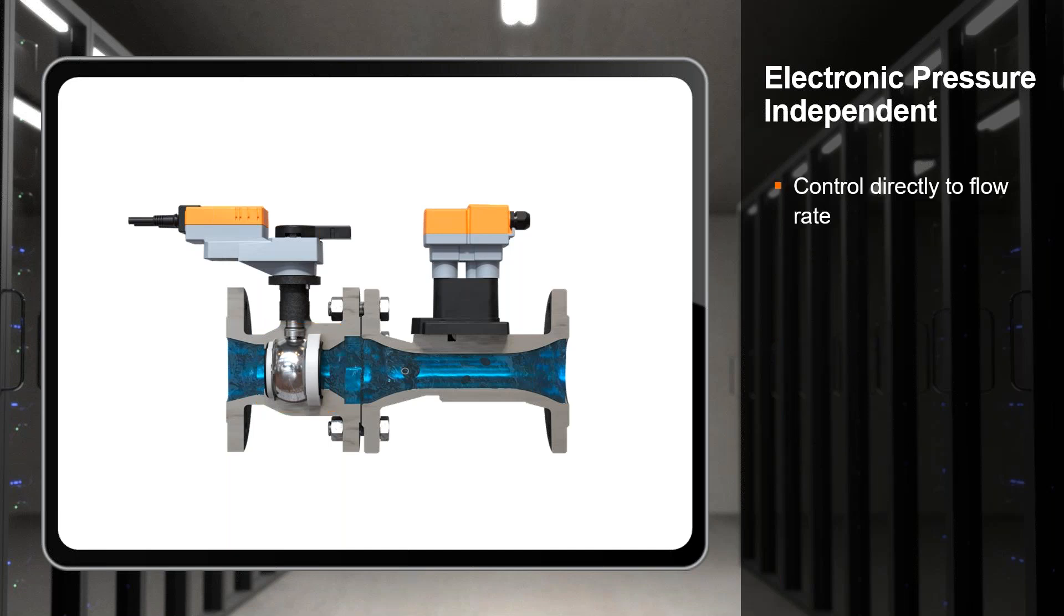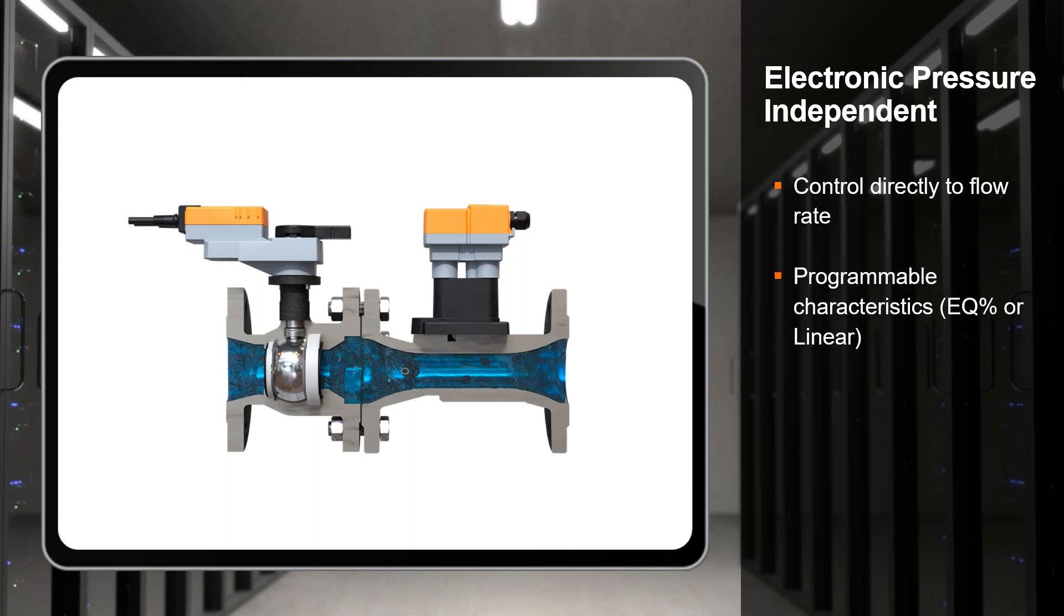There's a lot of advantages to utilizing the EPIV. Obviously we're going to control directly to a flow rate. If my rack of cold plates needs nine gallons a minute, I want nine gallons a minute - whether all the other cold plates are running, whether none of them are running, whether there's high pressure in the pump, whether there's low pressure in the pump, whatever is going on in that circuit. I want nine gallons a minute to my cold plates, nine gallons a minute to my rear door heat exchanger, or nine gallons a minute going into my immersion pool. The point is we want specific flows and that's what we can do here.